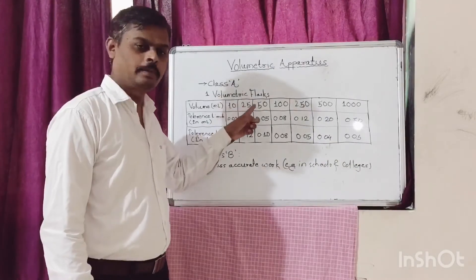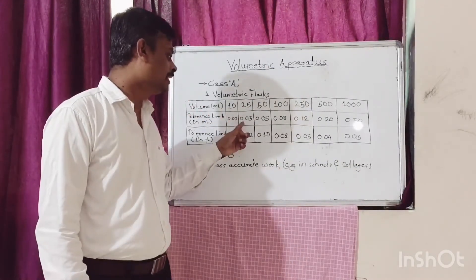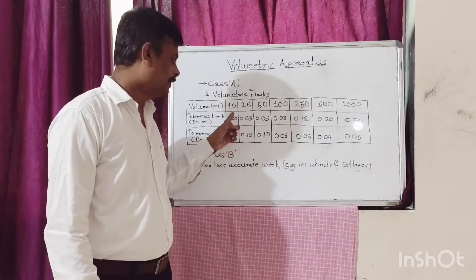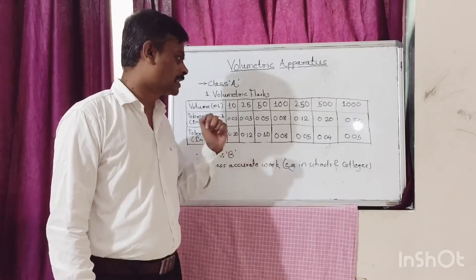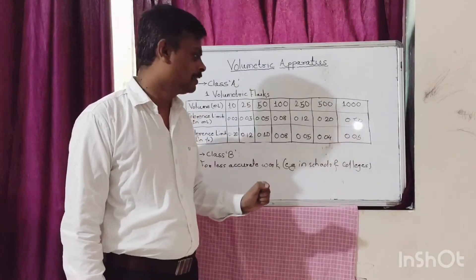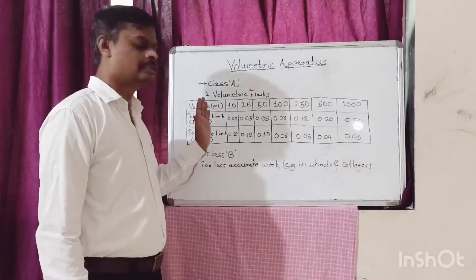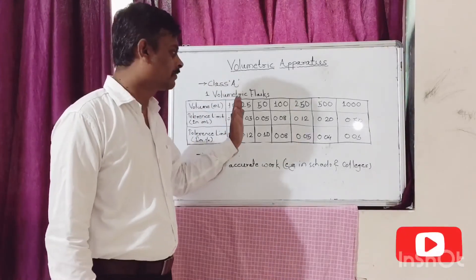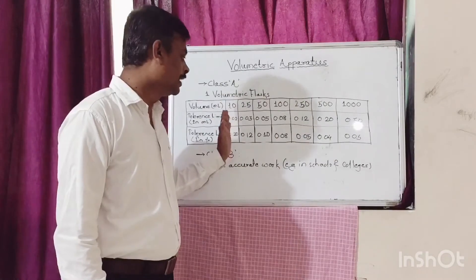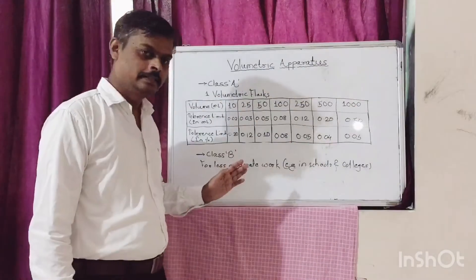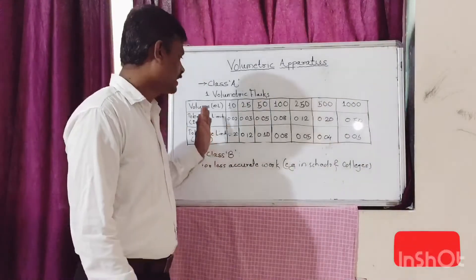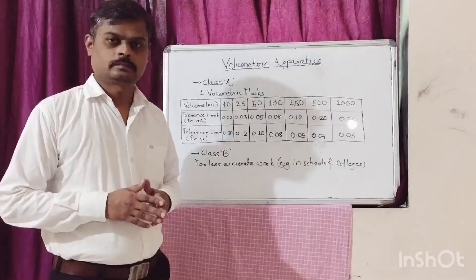Similarly, for 25 ml volumetric flasks, the tolerance limit in ml is plus or minus 0.03 ml. For 1000 ml, the tolerance limit in ml is plus or minus 0.30 ml. From this table, you can see that as the size of volumetric flasks increases, the tolerance limit in ml also increases. However, the tolerance limit with respect to percentage gradually decreases as the size of the volumetric flask increases.